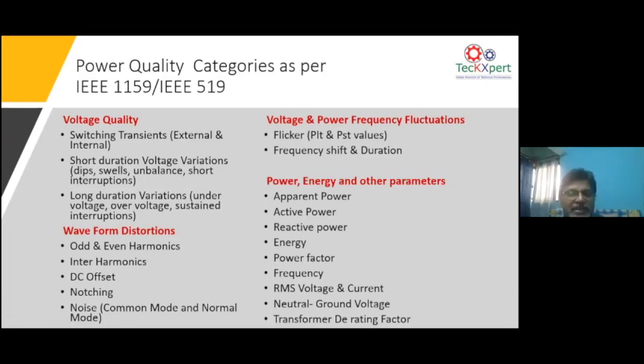Sometimes the lightning can create an impulse transient. That means it will only have a single polarity. It will only be on the positive cycle. Sometimes an impulse can be on the negative cycle, but it will not be oscillating. But then a short duration voltage variation is like your voltage sag and swells, temporary short interruptions. These things can be short duration voltage variation. When it comes to long duration, undervoltage and overvoltage are all long duration variations on voltage quality.